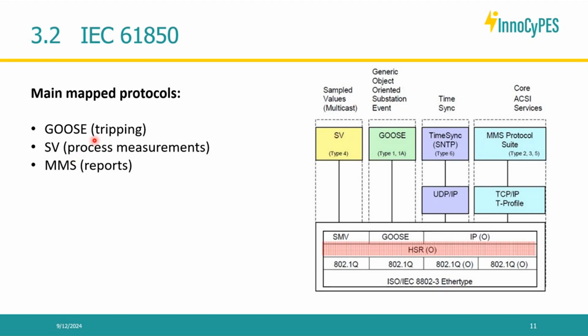GOOSE is a protocol that's also multicast, and it's supposed to send tripping signals mainly between IEDs within very small thresholds of 3 milliseconds, to respect the transfer time of the standard. These two protocols are important to keep in mind, because in the rest of the presentation I'll be referring to them during the different security considerations and attacks that can happen.